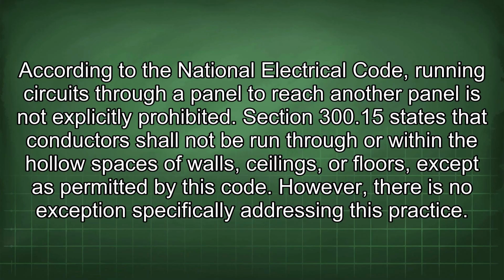According to the National Electrical Code, running circuits through a panel to reach another panel is not explicitly prohibited. Section 300.15 states that conductors shall not be run through or within the hollow spaces of walls, ceilings, or floors, except as permitted by this code. However, there is no exception specifically addressing this practice.